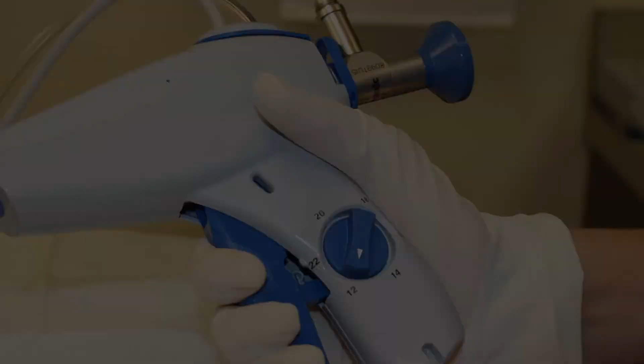It is important to note that the needle length selection dial on the handpiece is designed to turn counterclockwise from 12 up through increasing lengths to 22, or alternatively clockwise from 22 down through the decreasing lengths to 12 to set the appropriate needle length. Forcing the dial directly from 12 to 22 or vice versa may damage the dial. As a safety measure, deploy and retract the needles to test the mechanism before inserting them into the patient.